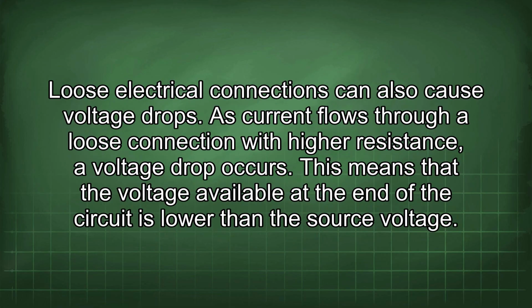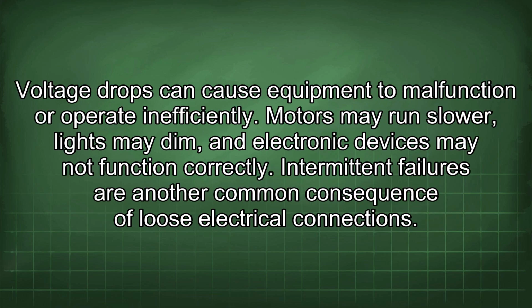Loose electrical connections can also cause voltage drops. As current flows through a loose connection with higher resistance, a voltage drop occurs. This means that the voltage available at the end of the circuit is lower than the source voltage. Voltage drops can cause equipment to malfunction or operate inefficiently. Motors may run slower, lights may dim, and electronic devices may not function correctly.